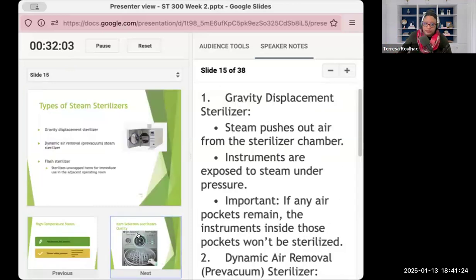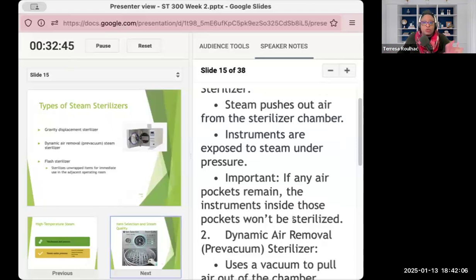Okay. We also have gravity displacement. A lot of smaller facilities will have these smaller instrument sets, a lot of times in dental, so a lot of oral maxillofacial places that only do those. They're going to have smaller sets, or smaller autoclaves. Now, with gravity displacement, steam is pushed out from the sterilizing chamber. Instruments are exposed to steam under pressure. You're going to hear me say that a lot. Exposure. So they're exposed. Now, if any air pockets remain, those instruments inside those pockets will not be sterilized.